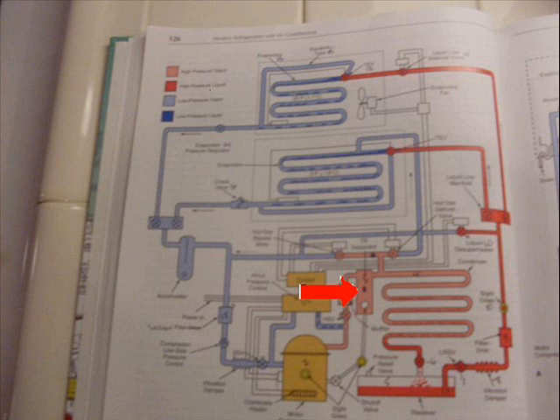The oil separator has an oil return flow valve in it. When the oil builds up, the high side pressure pushing down on the level of the oil with the float valve open will force the oil back to the low pressure side of the compressor.